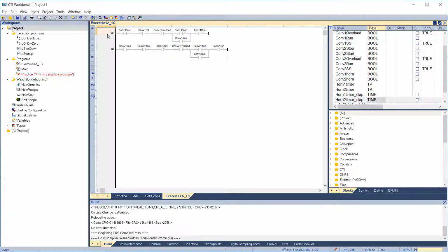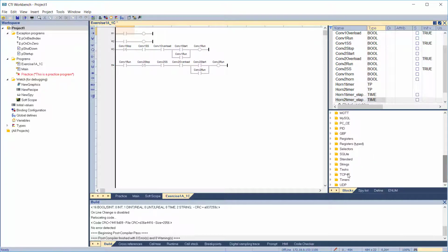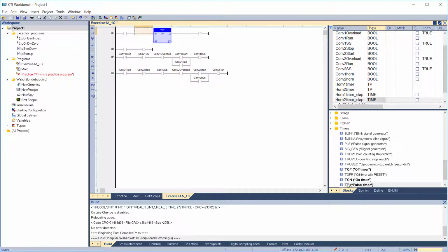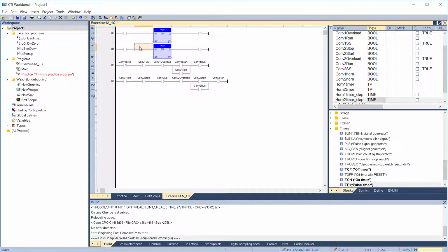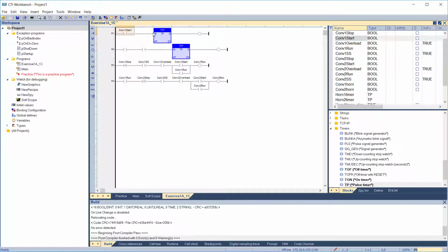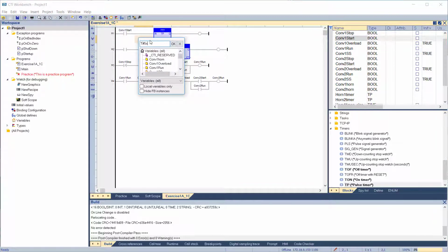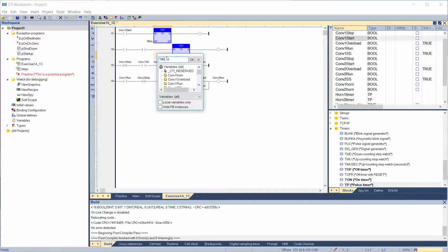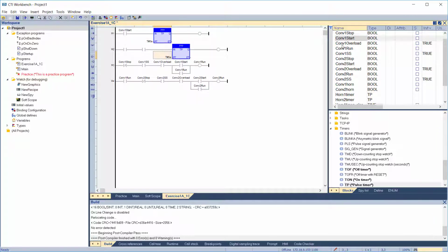To operate the horn timers, we'll add two rungs to our ladder diagram, one for each timer. Then, insert a pulse timer in each rung. The conveyor 2 rung will have an extra contact, so we can make sure conveyor 1 is running before starting conveyor 2. Put the conveyor 1 start switch on the first rung. Set the timer for 5 seconds. And attach the horn 1 contact. Then attach variables to rung 2, and attach the elapsed time variables.